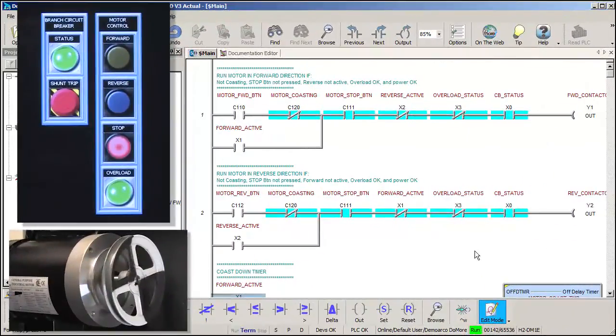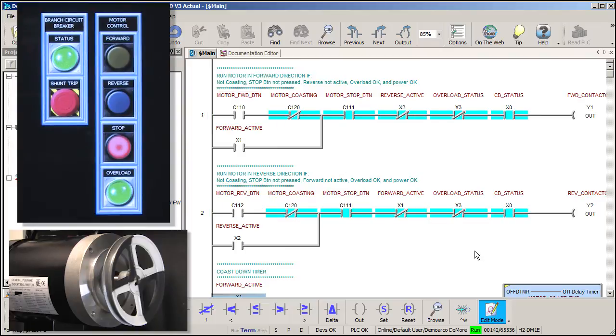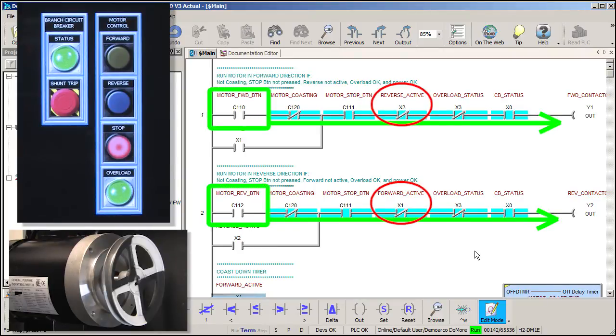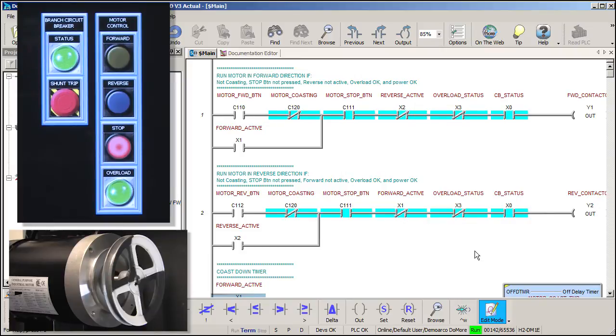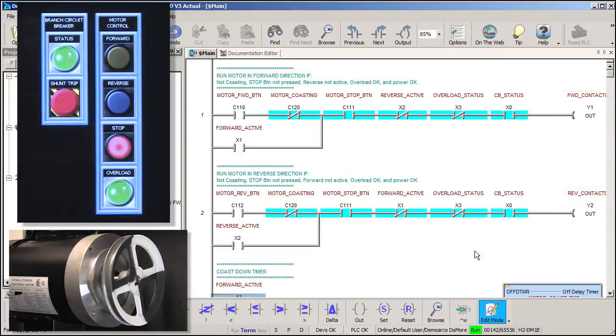This all looks great, but there is a potential problem. What happens if the user presses both the forward and reverse buttons at exactly the same time, or even just real close at the same time? Well, the power will flow through all these contacts on both the forward and reverse rungs, because their respective aux contacts won't have closed yet. It can take an aux contact 10 or 20 milliseconds to close, which means we won't see that feedback until many scans later. Which means both of these outputs will fire, which will engage both contactors, which will short out the power mains. And that's a bad thing, right?